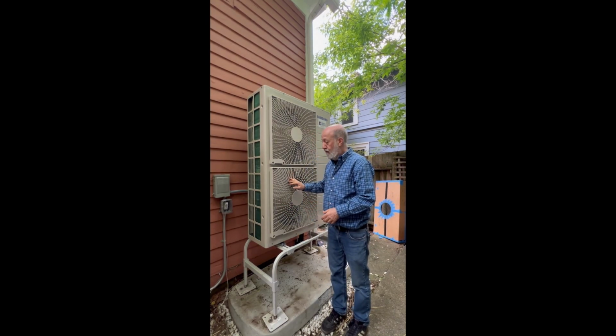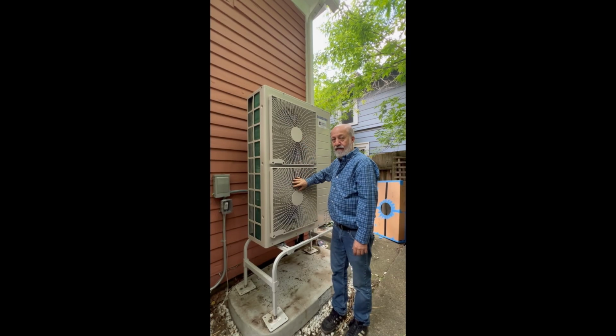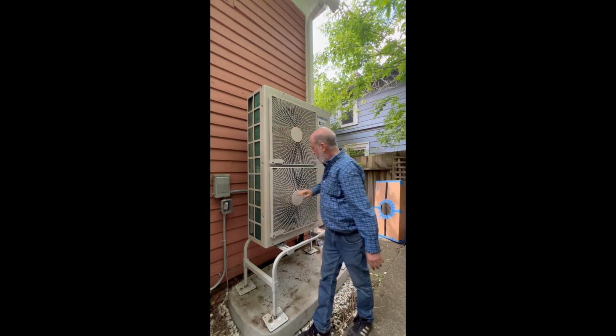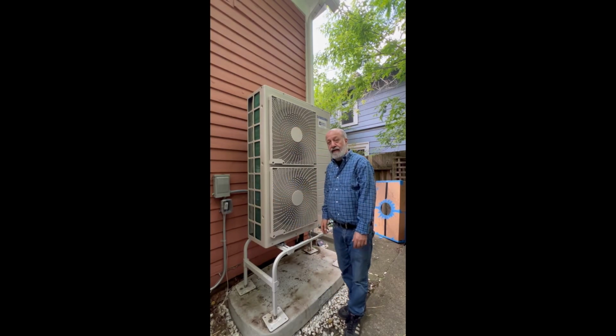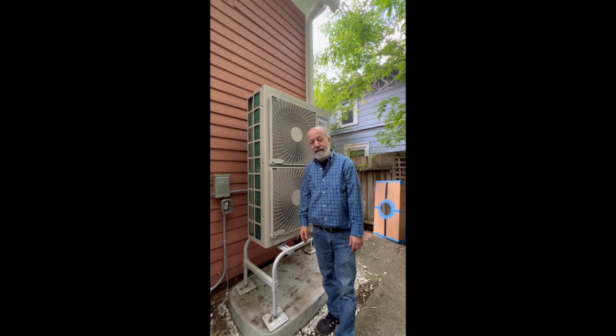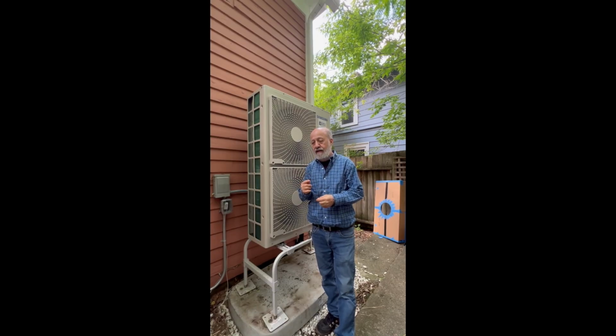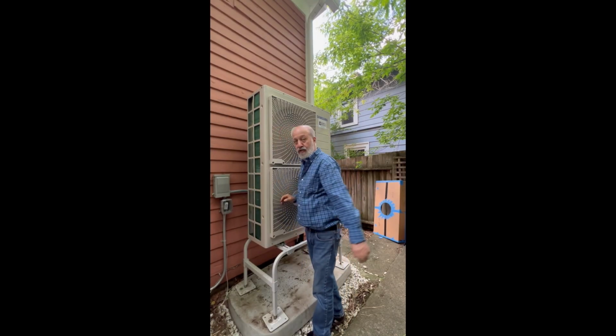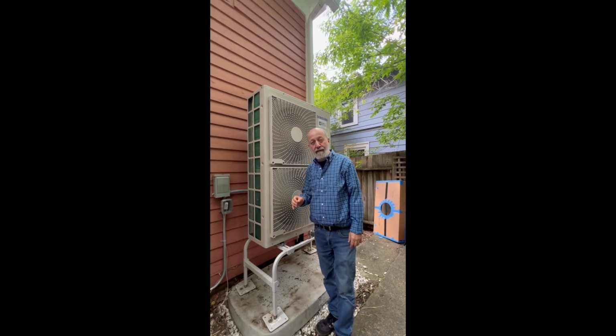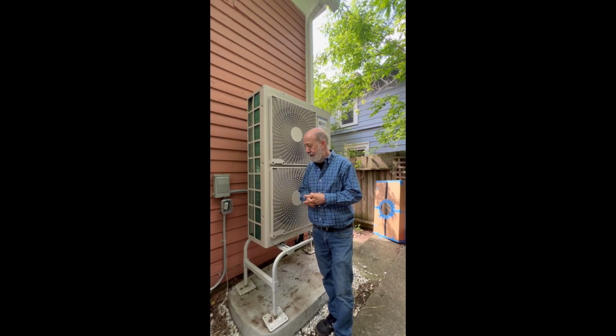This unit is actually running, and the whole heat pump outdoor unit, fans, heat exchanger, and in here, compressor and controls. Now what we've been examining is what we call air bypass. It's the movement of air around the heat exchanger. We want all the air to move through the heat exchanger, but what we've discovered is that some air, in fact a measurable fraction, bypasses. And we'll show you some of those bypass locations.